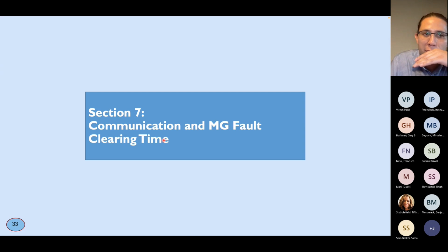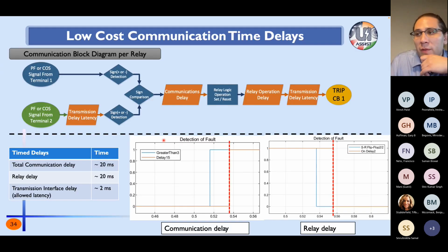The last section shows communication and fault clearing times. In communication, there is a transmission line delay, a communication delay, the relay operation delay, and the transmission latency, after which we are able to trip a circuit breaker when there is a sign of tripping. Here we show when a fault happens, how it is seen by each of the different relays, and when it trips. We can see that it trips within the margin we were expecting. Communication takes 20 milliseconds, the relay delay 20 milliseconds, and the latency another 2 milliseconds. The bottom shows the communication delay and here the relay delay, as shown in the different steps of the block diagram.